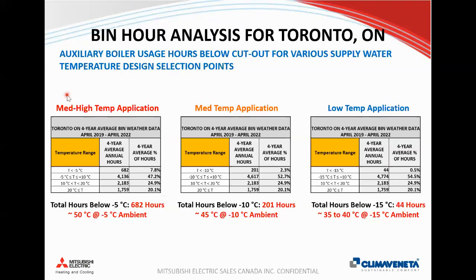So again, I was alluding to weather data before. So depending on the application and the supply temperature that you're going to use in your system, that will kind of dictate how you're going to size your heat pumps. But what I like to show is the total amount of time we spend below that imaginary cutout temperature. So if you had a medium to high temperature application where you do need a lot of high temperature hot water that's required, usually I recommend try to design for about a -5 degrees Celsius cutout, because these machines can typically give you about 48 to 50 degrees Celsius here.